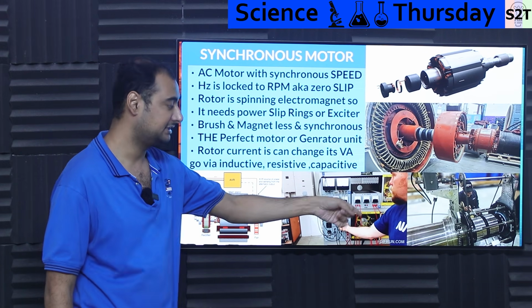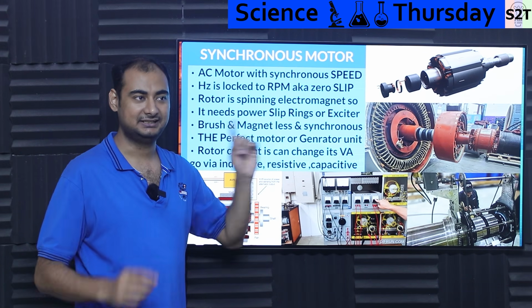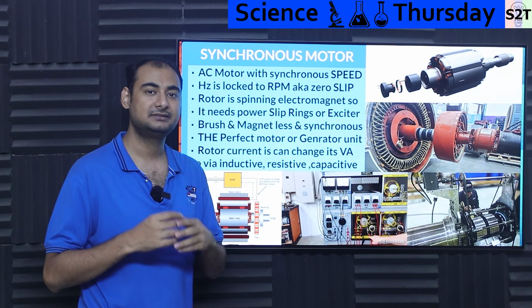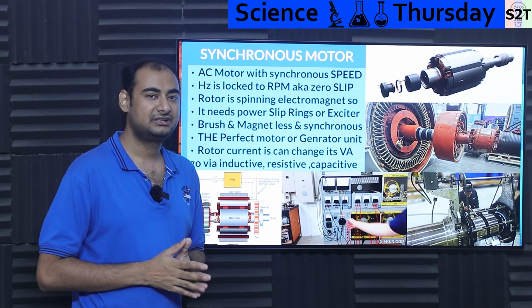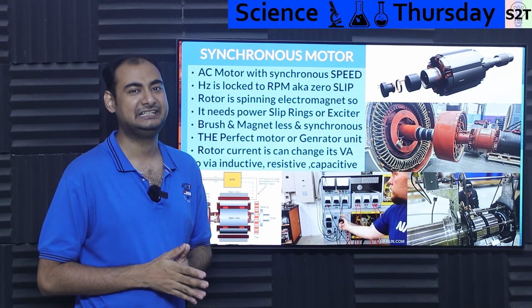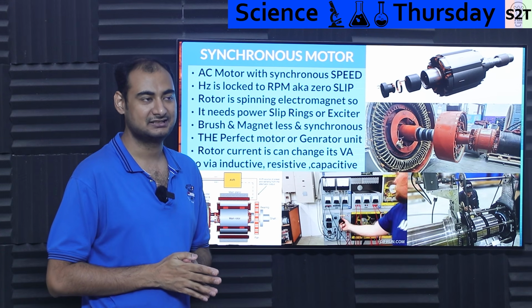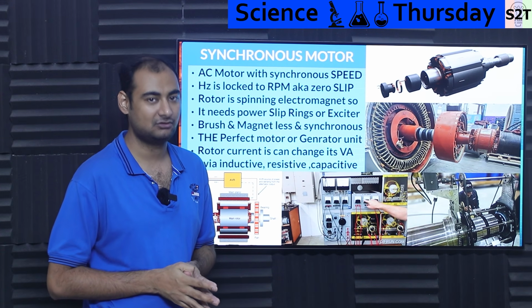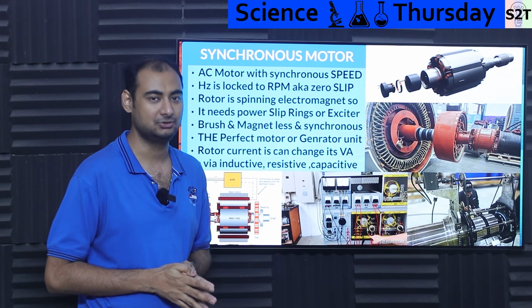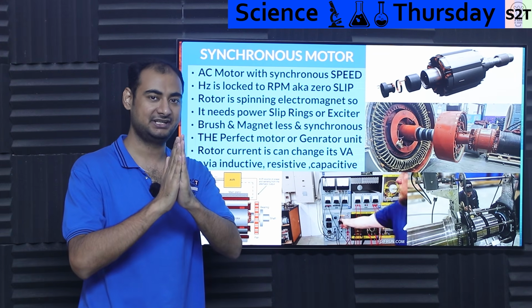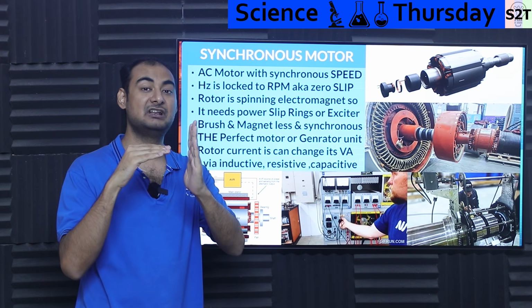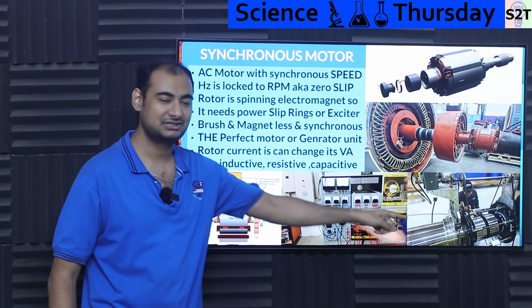This is awesome, but it does have the penalty that it has to be a stable system, because those brushes in power plant structure do not have amps going through them - they have kilo amps going through them, and some designs have thousands of kilo amps, let that be very clear. Those puppies are huge, meaning if you have a minor deviation on the bearings, it will not create an arc, it will weld it. So fundamentally, those things require very precise precision, you cannot just lull it.